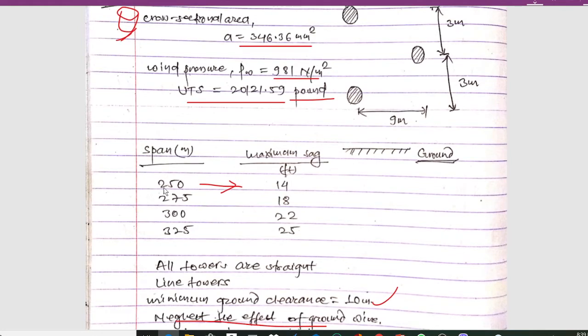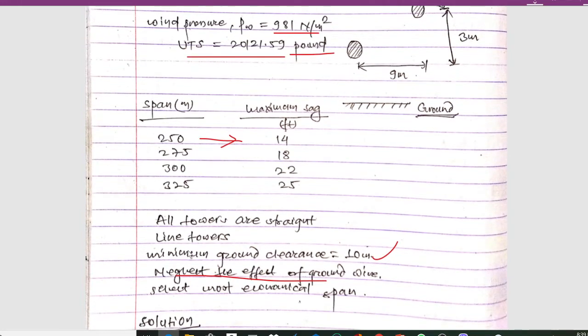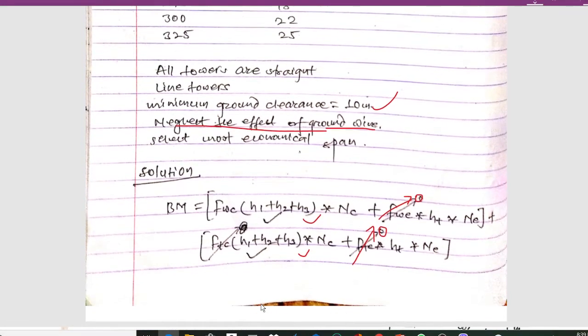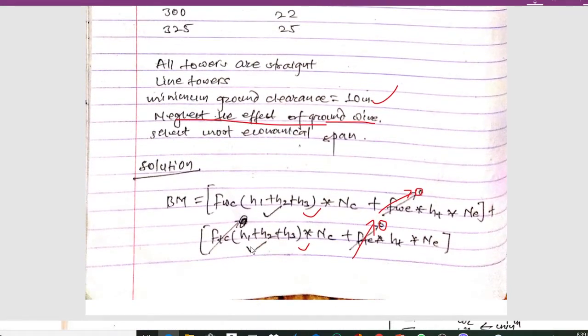The span and respective maximum sag values are given in a table. In this question, all towers are straight line towers, minimum ground clearance is given as 10 meters, and we have to neglect the effect of ground wires. We need to select the most economical span. Since we neglect ground wires, the bending moment is calculated using the relevant formula.